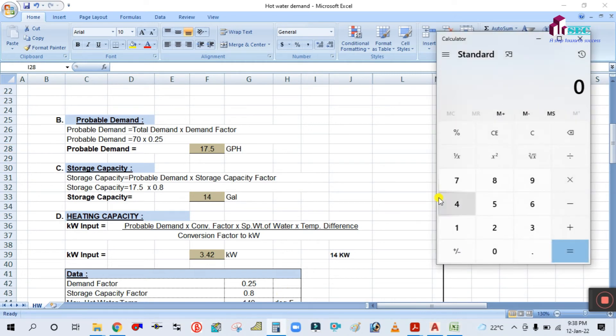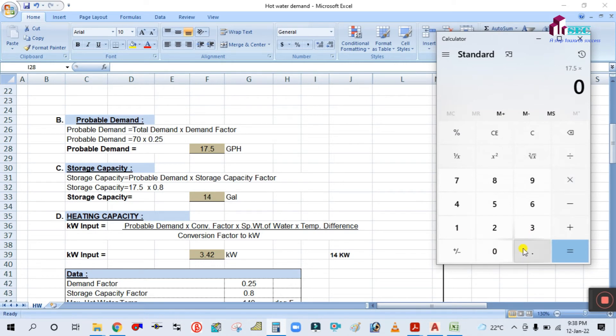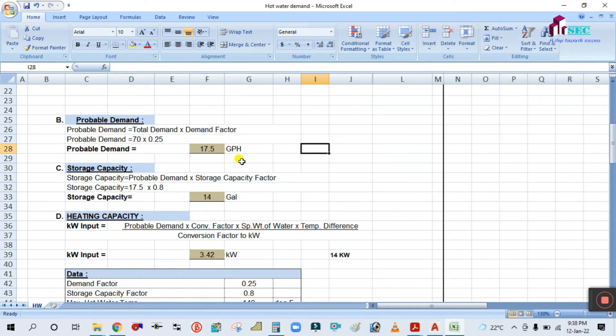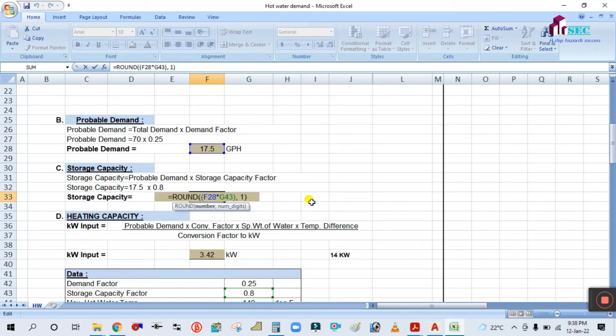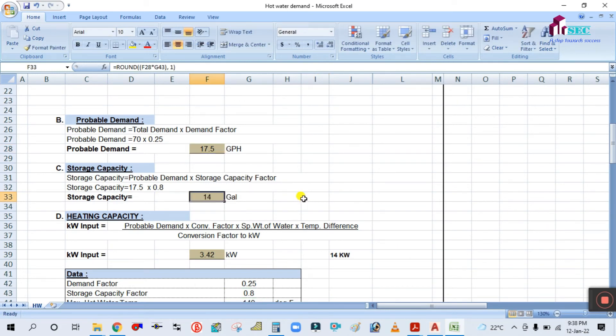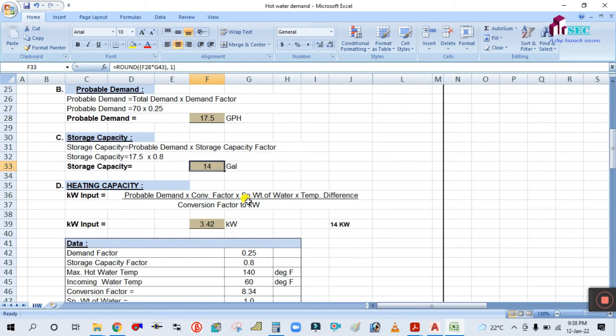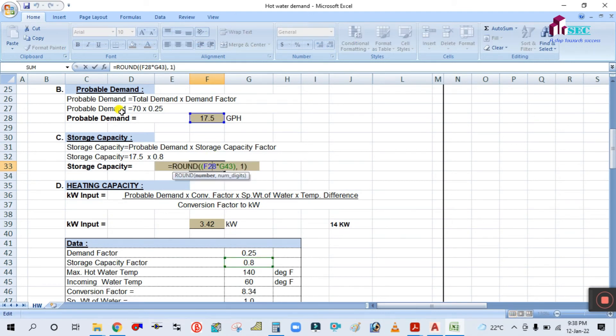So storage capacity = 17.5 × 0.8 = 14 gallons. Here is the 14-gallon result. Because this cell already has the formula: probable demand × storage capacity factor.